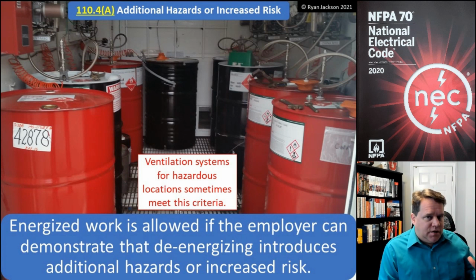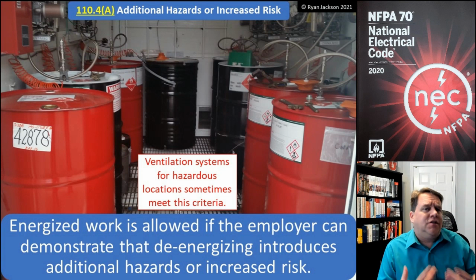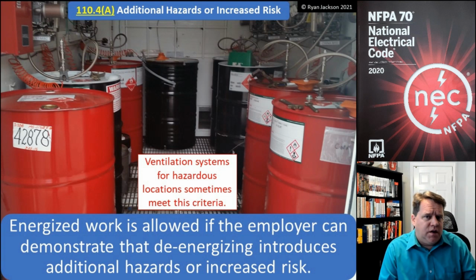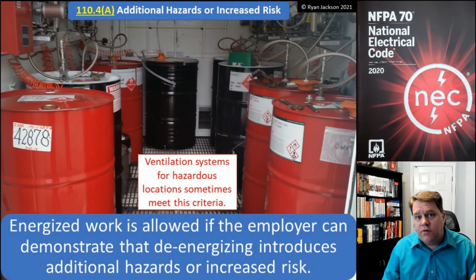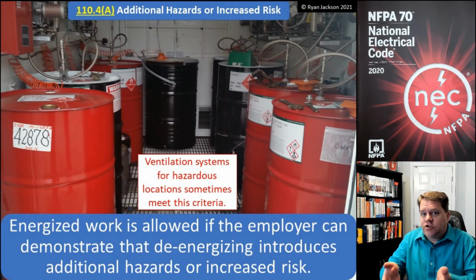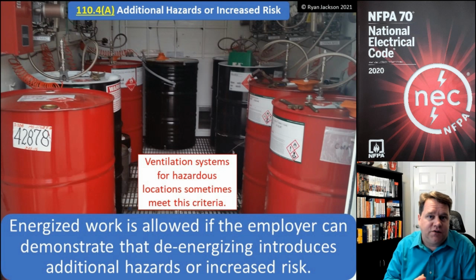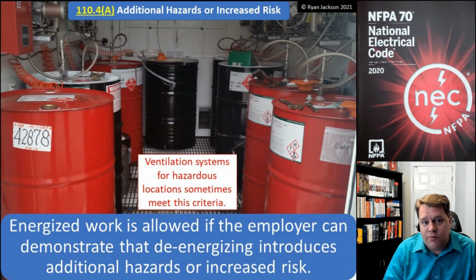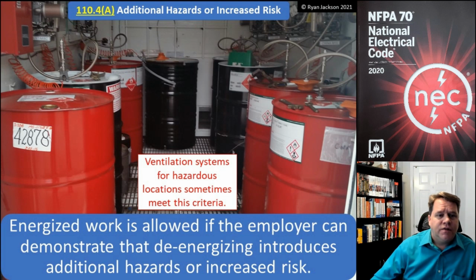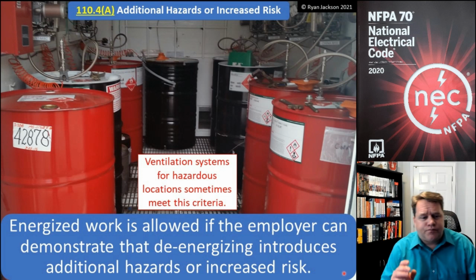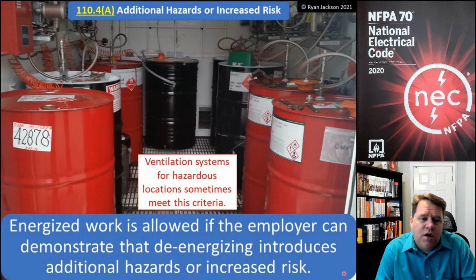What if you can't shut the equipment down? Is it ever allowed to work on energized equipment in 70E? Well, yes. The 70E doesn't say thou shalt shut everything down in all instances. There are times when that's not possible. So when are you allowed to work energized according to 70E? Well, that's where we get into 110.4, additional hazards or increased risk. Energized work is allowed if the employer can demonstrate that de-energizing the equipment actually introduces additional hazards or increased risks.